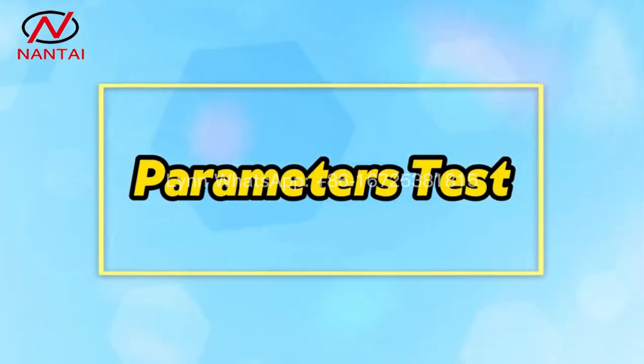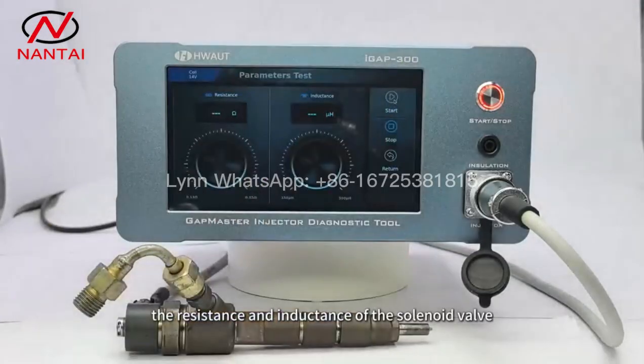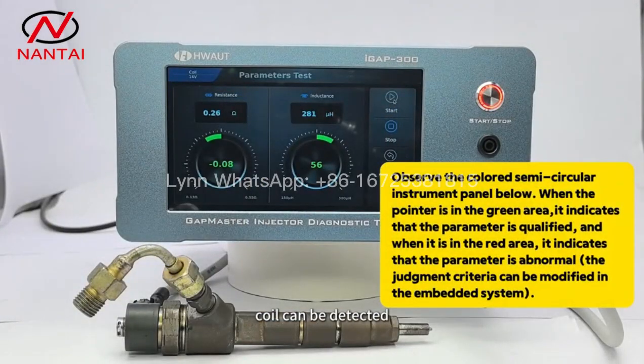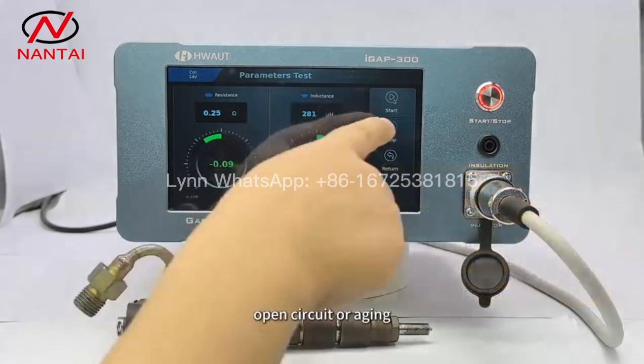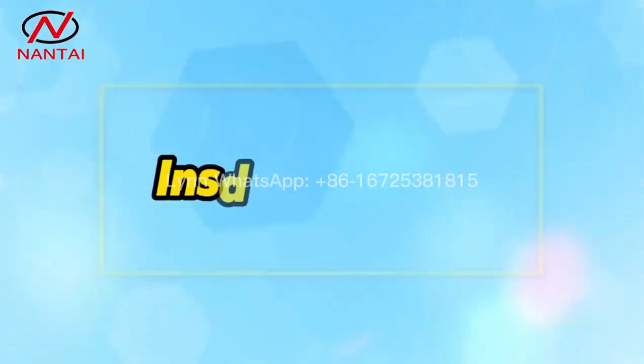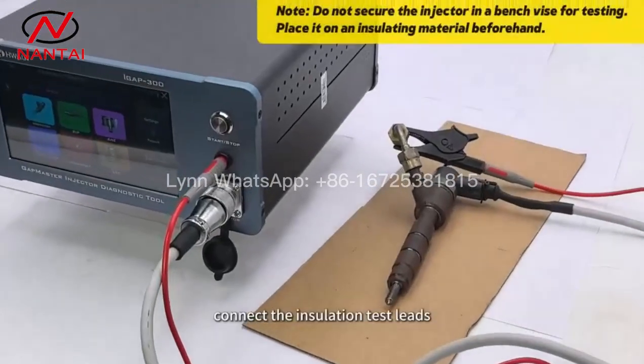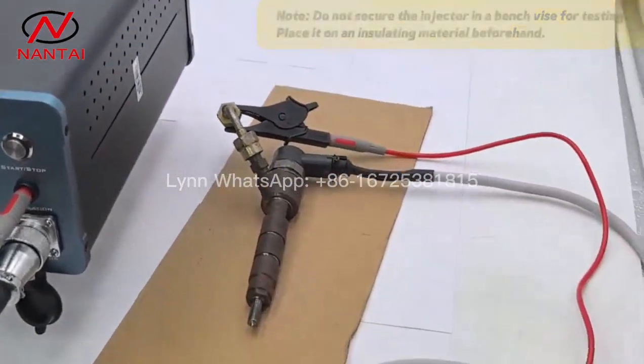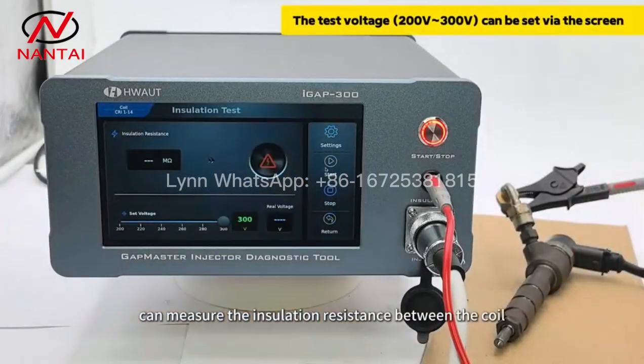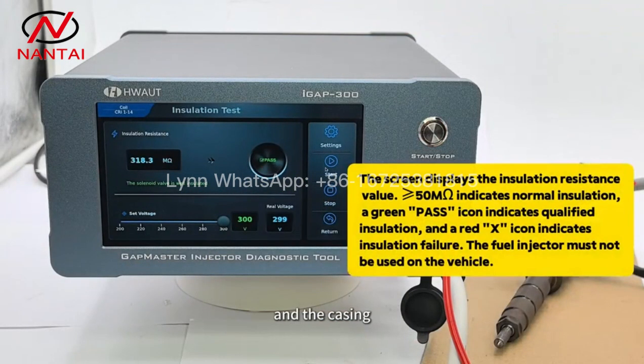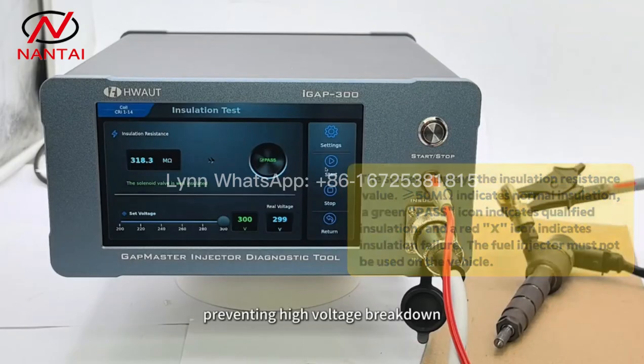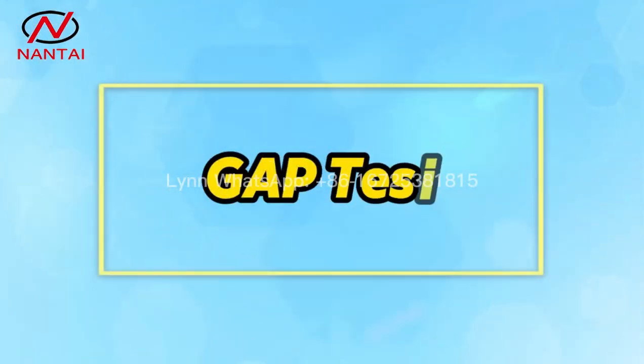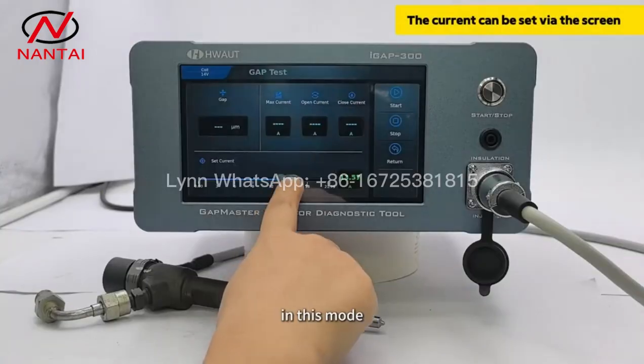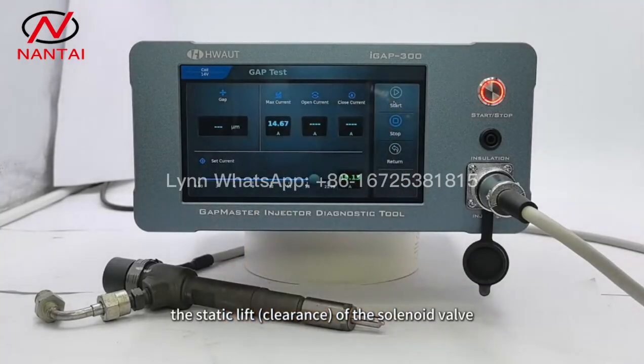Parameters test. In this mode, the resistance and inductance of the solenoid valve coil can be detected to determine whether there is a short circuit, open circuit, or aging. Insulation test. Connect the insulation test leads. This mode can measure the insulation resistance between the coil and the casing, preventing high voltage breakdown. Gap test. In this mode, the static lift clearance of the solenoid valve armature can be measured.